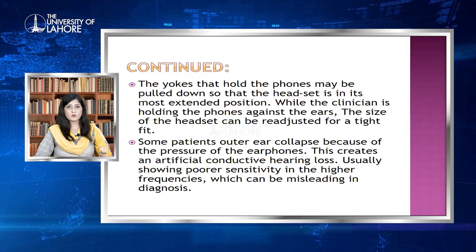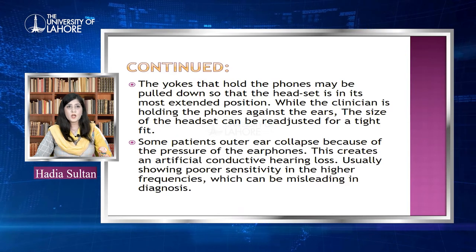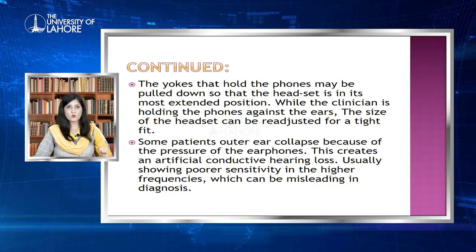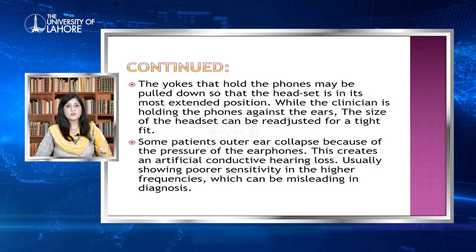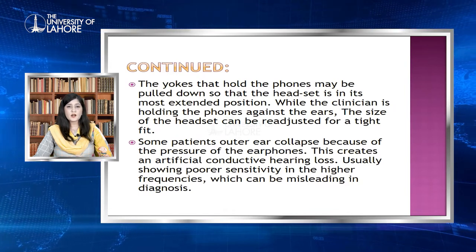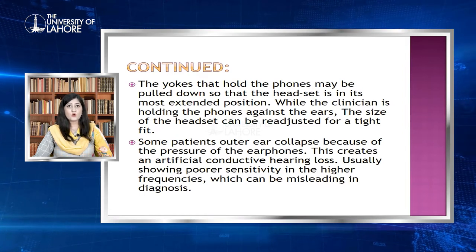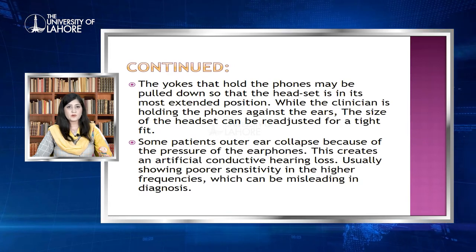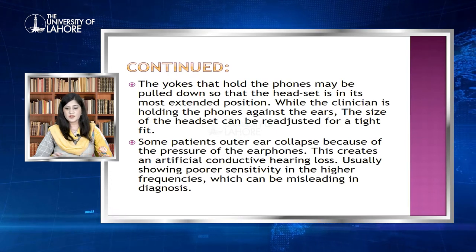The yokes that hold the phones may be pulled down so that the headset is in its most extended position. While the clinician is holding the phones against the ears, the size of the headset can be adjusted for a right fit. Some patients' outer ear may collapse during placement, causing an artificial conductive hearing loss which can mislead the diagnosis. If not placed properly, it can cause the appearance of conductive hearing loss — which would be a wrong diagnosis.